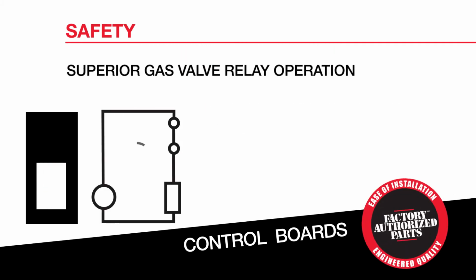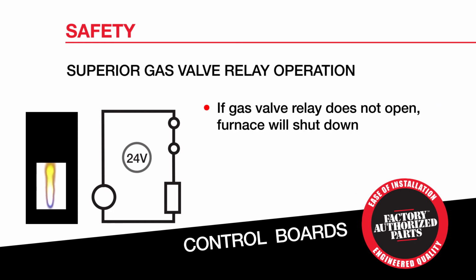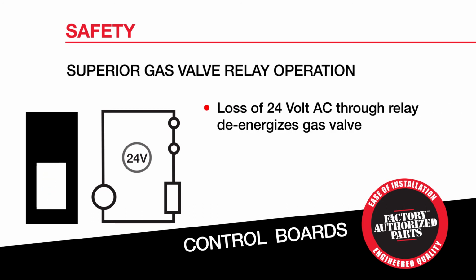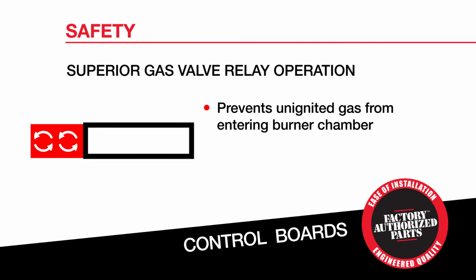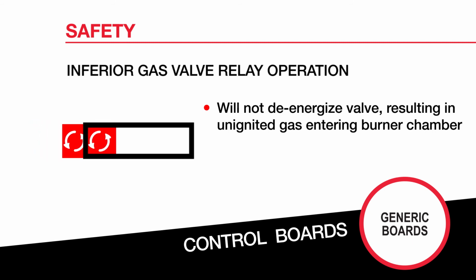Factory authorized parts boards feature superior gas valve relay operation. At the end of a call for heat, if the gas valve relay in the control board does not open, the control board will detect voltage through the closed relay and shut the furnace down. The loss of 24-volt AC through the gas valve relay will de-energize the gas valve. This prevents unignited gas from entering the burner chamber. Some generic boards will not de-energize the valve in the same scenario, which can result in unignited gas entering the burner chamber.